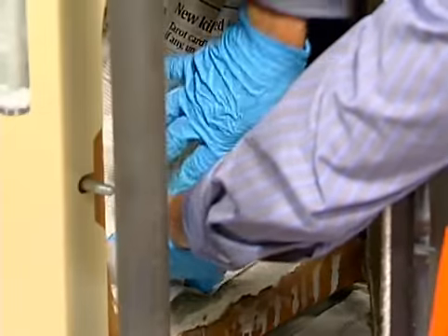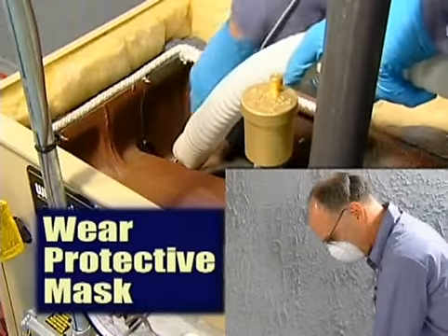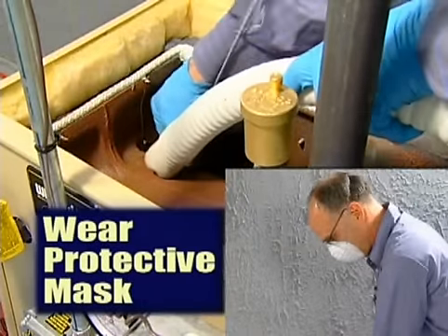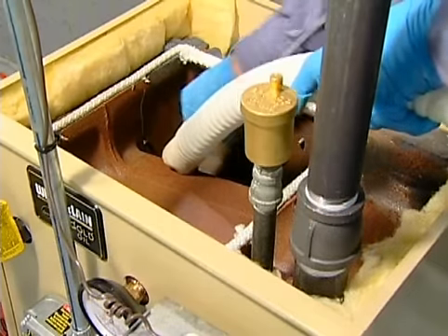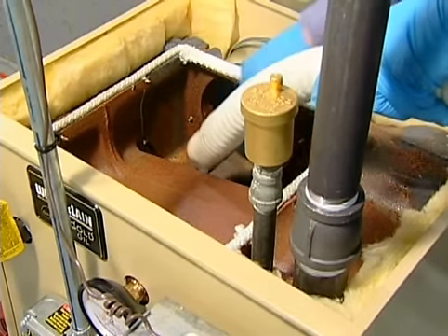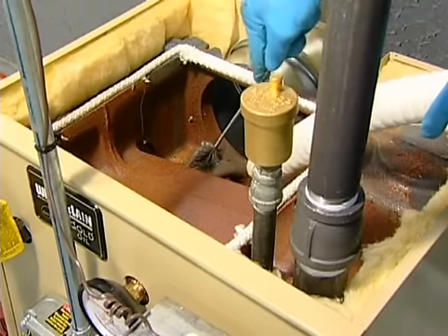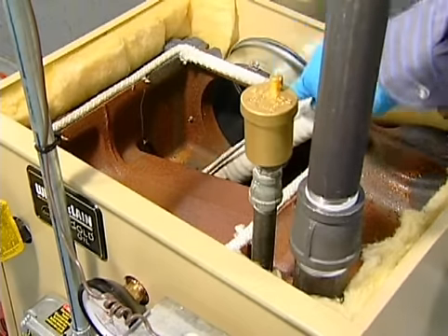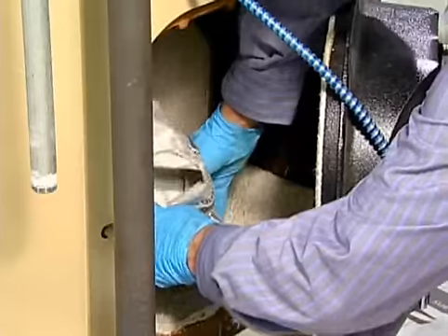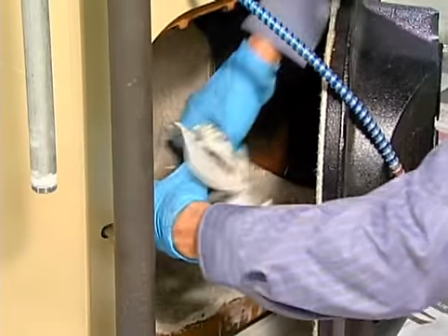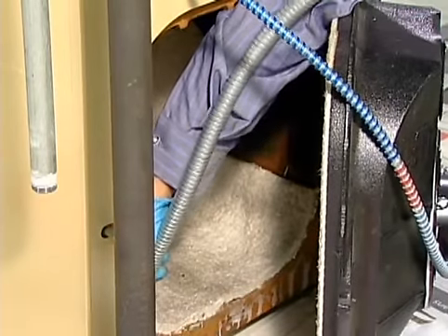Scrub the flue passes, keeping your vacuum hose close to the brush to avoid spreading soot. If this were a steel boiler, you would first have to remove the baffles, then brush the tubes. Make sure to look for any signs of air or water leaks. Use a soot snorkel to clean the combustion area, being very careful not to damage the chamber or target wall. Inspect the condition of the refractory material and repair or replace it as necessary.